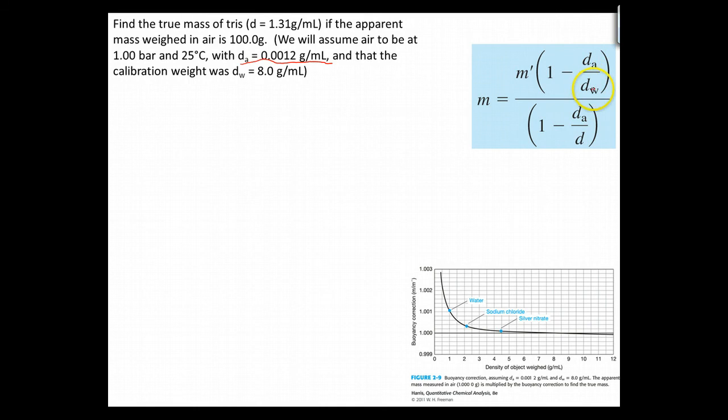And also how that's going to compare to some other object that was used to calibrate it in the first place. That's going to be the density of the weight they're going to use to actually calibrate our balance. Now, obviously, you're going to have some sort of a lead sinker or something like that that's already been well calibrated. Actually, in reality, it's usually brass or bronze or something like that. So you're going to put it onto the pan.